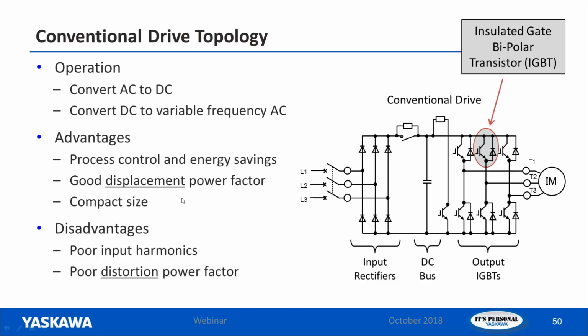So the advantages to this process are control and energy savings, and you get a good displacement power factor. And with VFDs, they are a pretty compact size now. Over the past 25 years, they've been able to get pretty small. Disadvantages, of course, are going to be poor input harmonics and poor distortion power factor. But let's take a look at that pulse width modulation I was talking about.